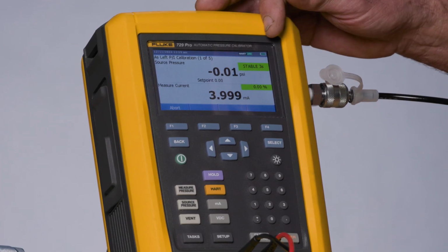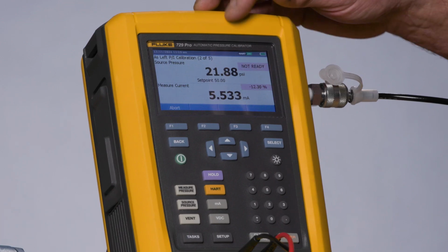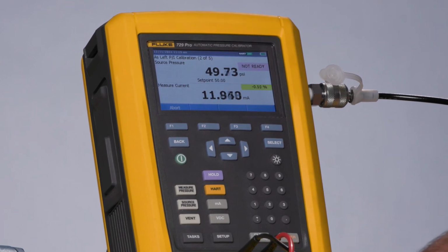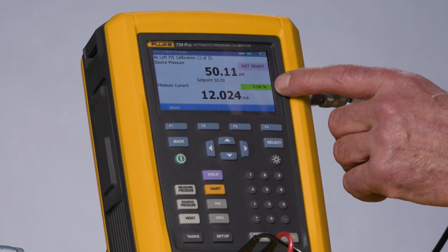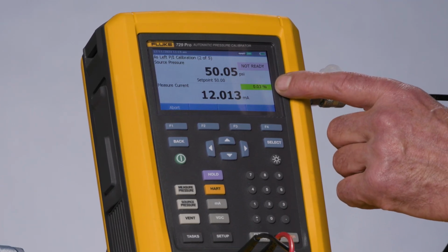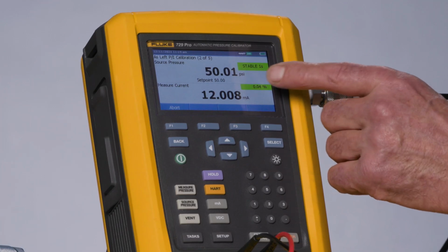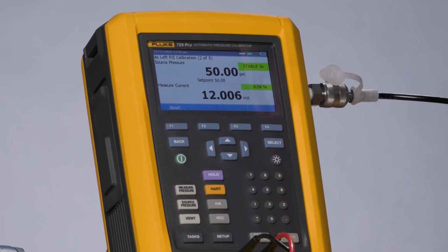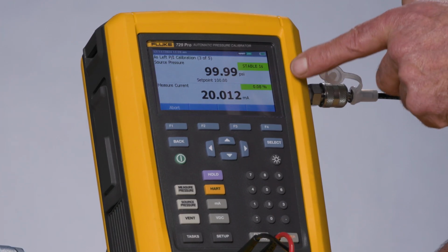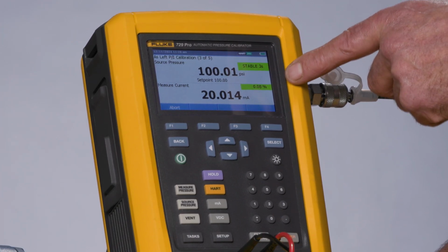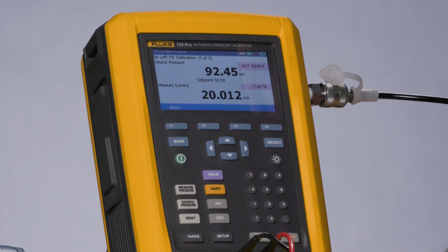The first point is recorded, the 0. Now it's going to go to the 50 psi and record the 50 psi milliamp measurement. Now notice, now the milliamp measurement is showing in green because the error, the deviation of the milliamp signal, is less than the designated test tolerance of 0.2%. psi, this goes stable, and then we'll start going down to the 50 psi point and complete the as-left test.